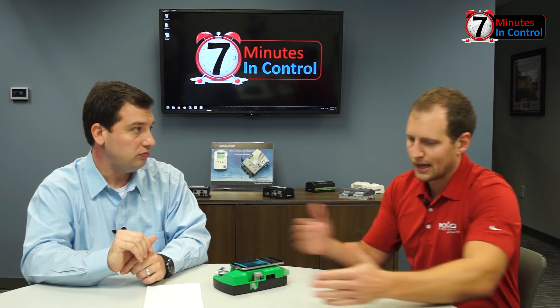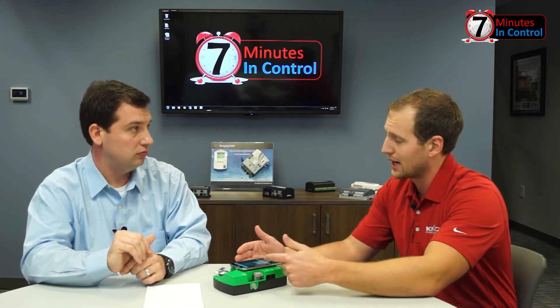Any kind of thing that you change, you can just write to the device. If you had a new controller, it's the same process — you're just placing your NFC-capable phone up there. There are some other nice features too. Say I had 10 VAVs in a row and I just sent the device with the MAC address of VAV 1 — simply hit the increment button, go to the next device, hit 'write to device,' and it increments everything so that you're getting your controllers online as quickly as possible.